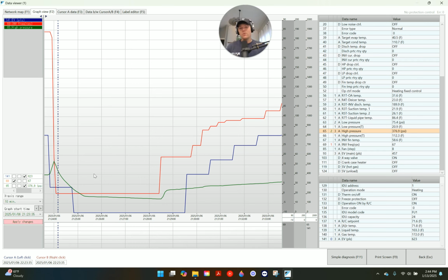Now, again, he recorded this for a decent amount of time and he never got an error code. But we see here in the data that it did exactly what it was doing before, which would have caused an error code had it done it 3 times in a row in that 60-minute window. Now, every piece of equipment is different. I'll obviously reference the service manual to find out what those windows are in which it trips.